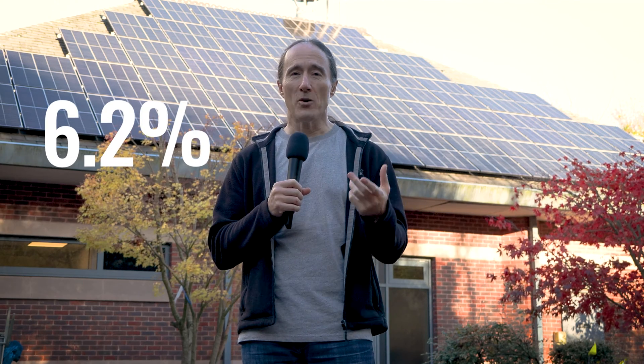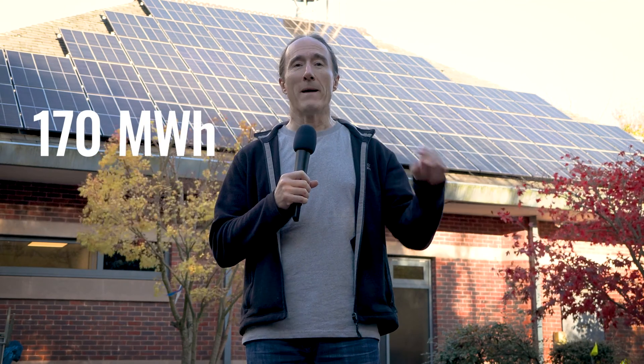Now, of course, October is after the autumn equinox, so days are shorter than average, so October is probably not an average month. So what I did is I went online to the EU's photovoltaic geographical information system to see how much for this particular location in Rochdale should be generated in October. According to that model, 6.2% of your annual generation should happen in October. So if 10.5 megawatt hours is 6.2% of annual, then that would make our annual expectation 170 megawatt hours. And that's really good news because the system was specced to generate 189 megawatt hours in a year — so that's 90% of what we expect.